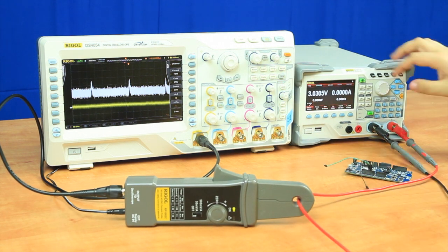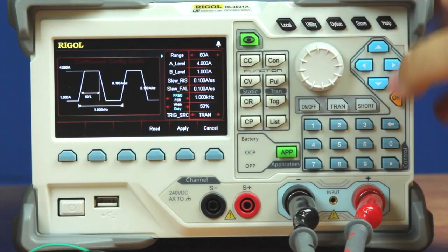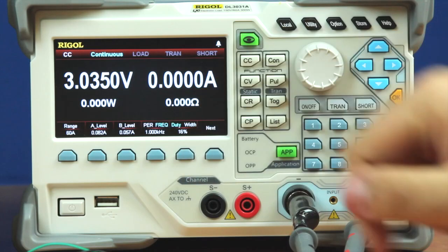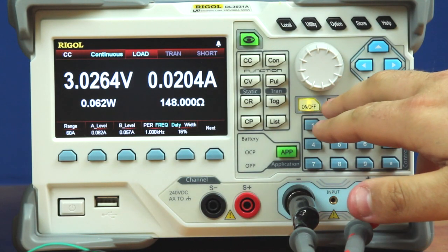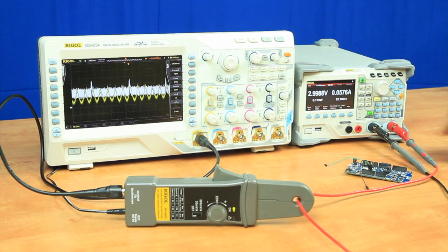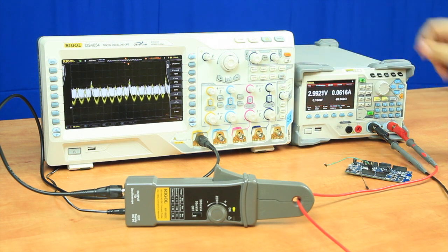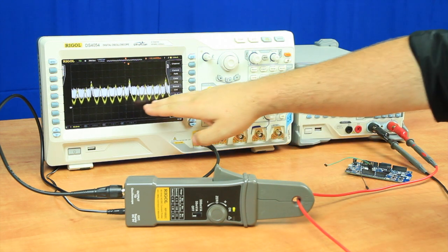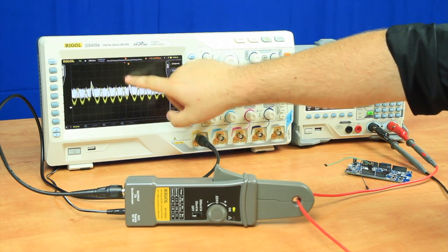Now that it's hooked up, we're going to go into continuous mode. In continuous mode, we're going to start setting levels just like before in our previous test and hit apply. Now we'll turn on the load, which will give us our vertical shift. We also have to turn on the spike, so we're going to hit the transient function and adjust our trigger a little bit. We're not quite perfect with our current floor, but we've certainly brought it up. We're closer on the top, and we've got our spikes better matching the spikes from before.